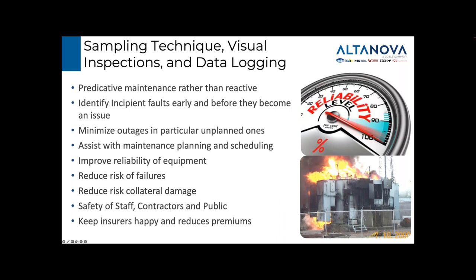Samples should be taken at condition-based intervals. There is some guidance on sampling frequency within IEC 60422, but the exact frequency should be modified based on voltage class, the current condition of the asset, and its criticality. Sampling should be accompanied by visual inspection done at the same time as the sampling. Keeping good records of maintenance or loading profiles is fundamental to good condition monitoring and maintenance scheduling. If you do own online DGA monitoring equipment, don't let this substitute for sampling activities. As listed in this slide, the benefits speak for themselves, in particular for reliability, safety, and of course, keeping insurers happy.